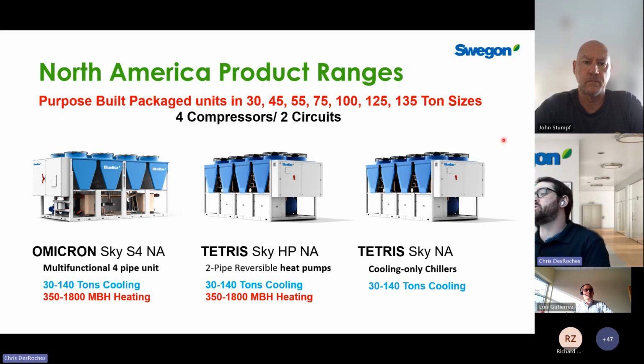So we have our Tetris line, which comes as a cooling-only chiller. If we have cooling dominant loads in our building, we might want to mix and match that with some reversible heat pumps. Under the Tetris family, we also have our 2-pipe reversible heat pump. So we're going to use this seasonally to make hot water all winter, chilled water all summer. If we have the requirement for heating and cooling available year-round, you're going to look at using our Omicron 4-pipe multifunctional unit, which is a heat recovery heat pump that is able to produce hot water and chilled water independently, but simultaneously, with a hot water and a chilled water set point.